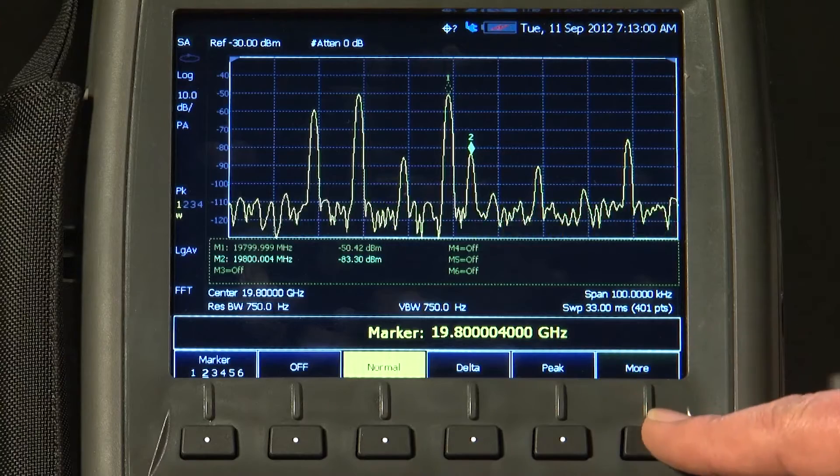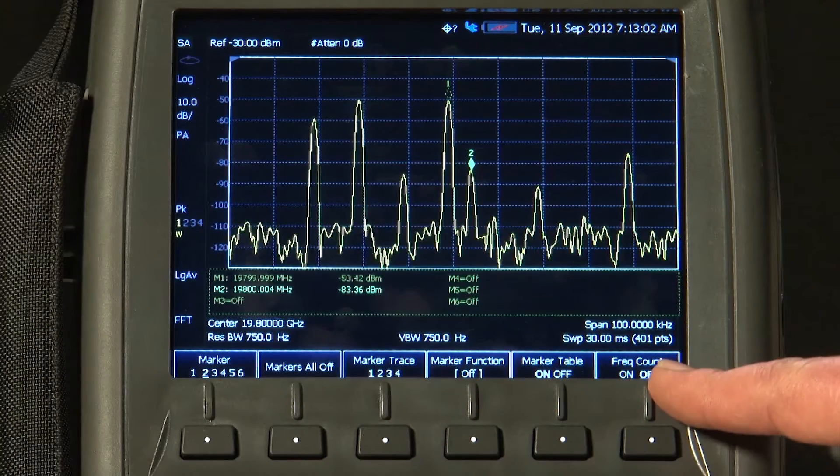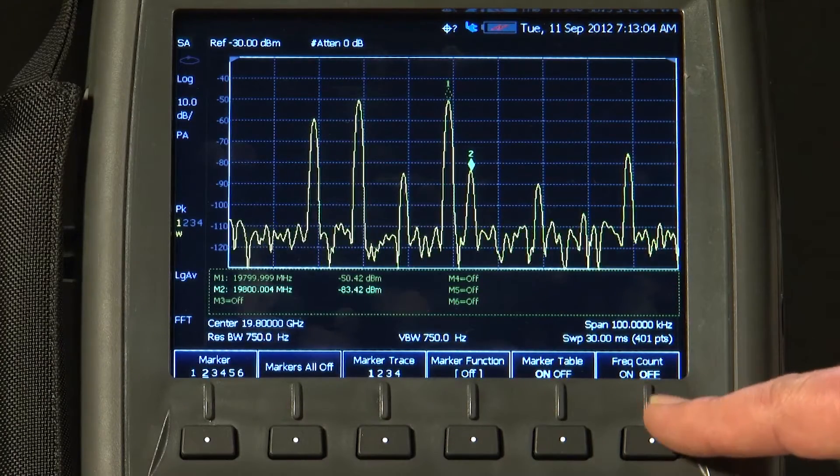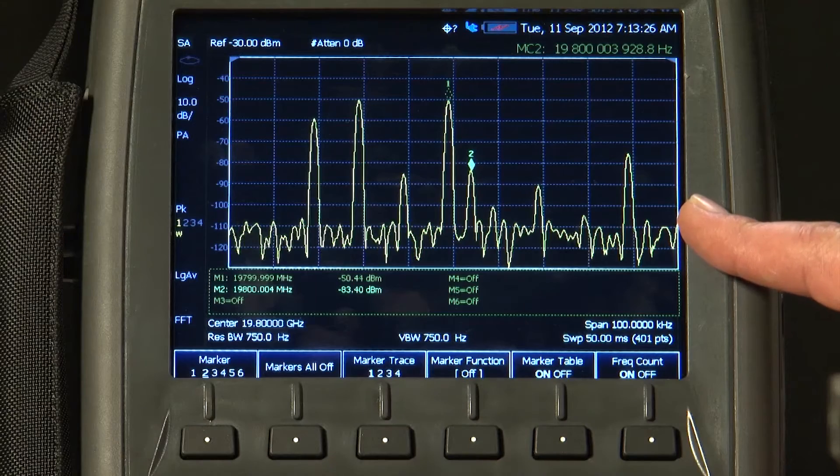If I press the marker button and then press More, you will see here on the right hand side it says Frequency Count Off. If I now turn that on, marker 2, which is the currently selected marker, has now activated a microwave frequency counter.